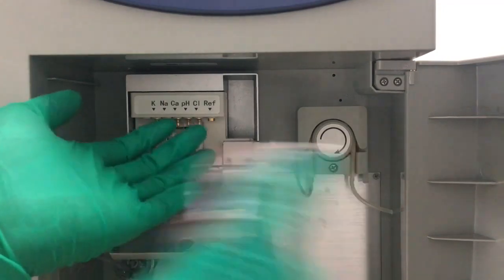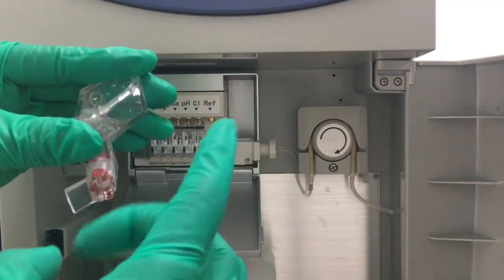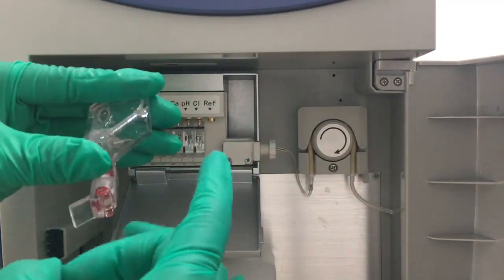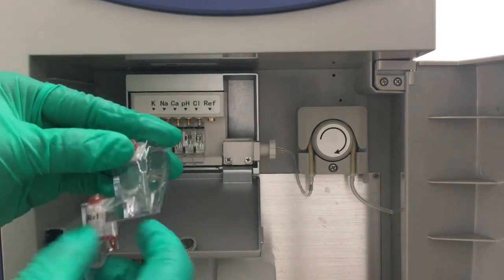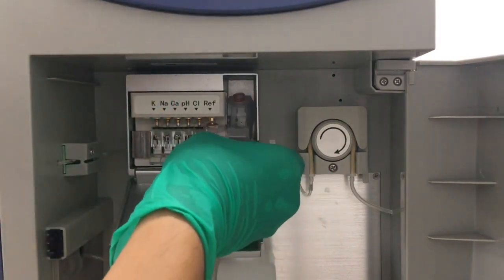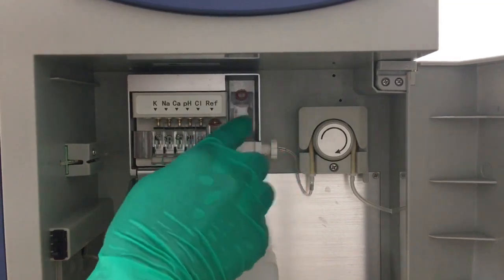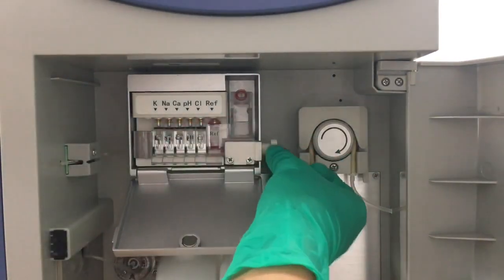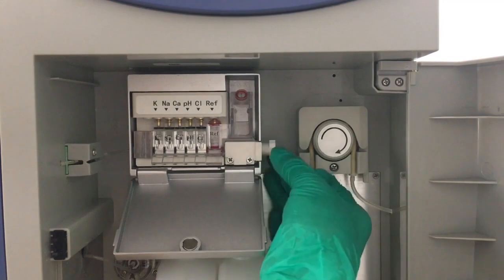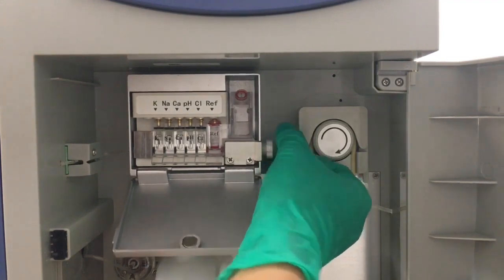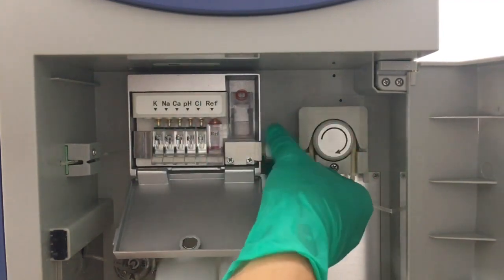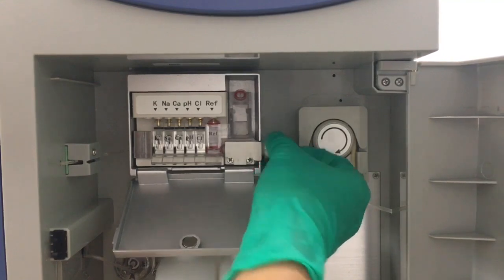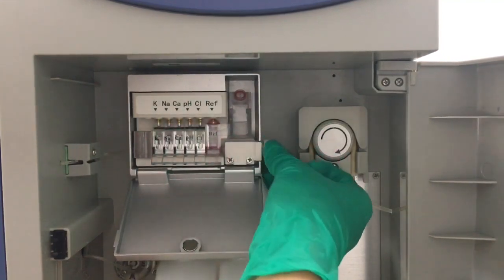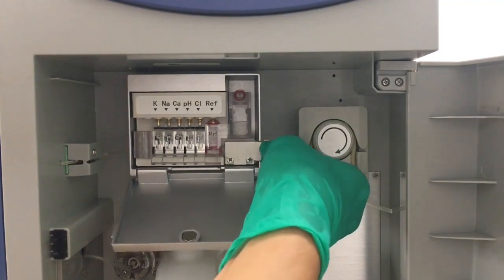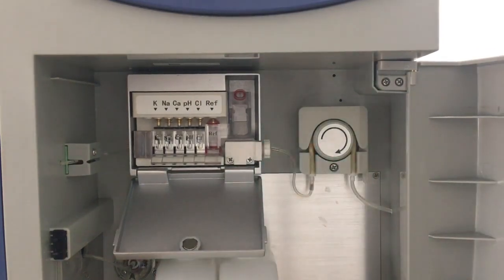And we hold it like this and use our palm to hit it, and flip the bottom of the reference electrode to remove the bubbles. Then we can tighten the knob. And we also need to press the electrodes to keep them in a line. We also need to pay attention not to fold the pipe.